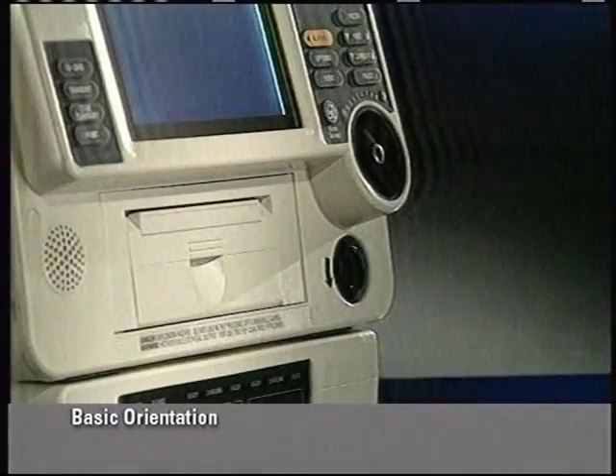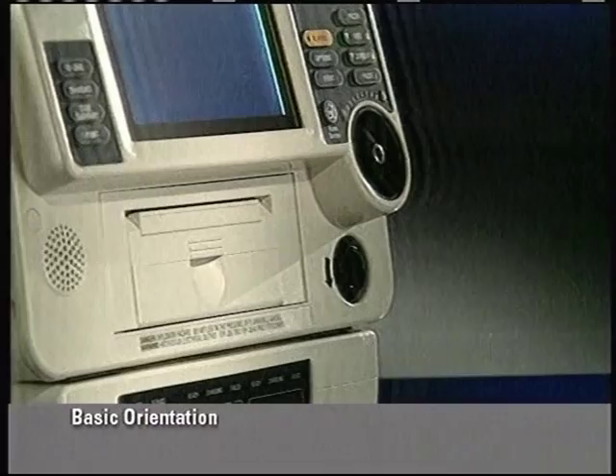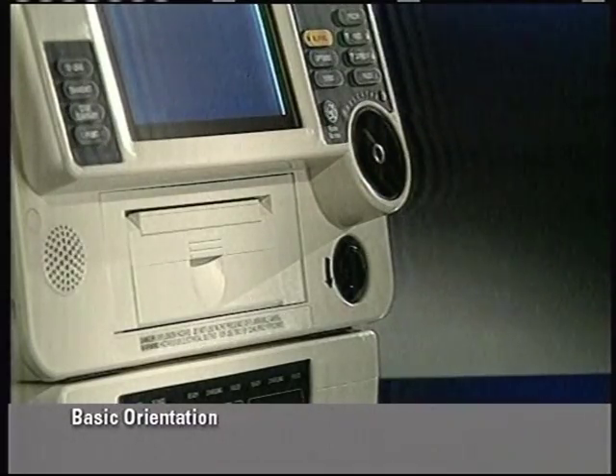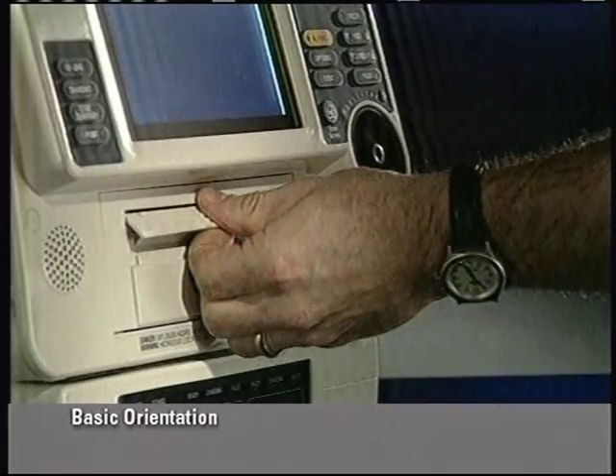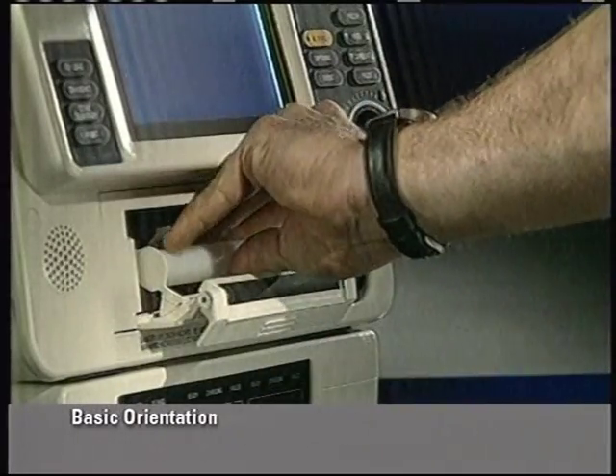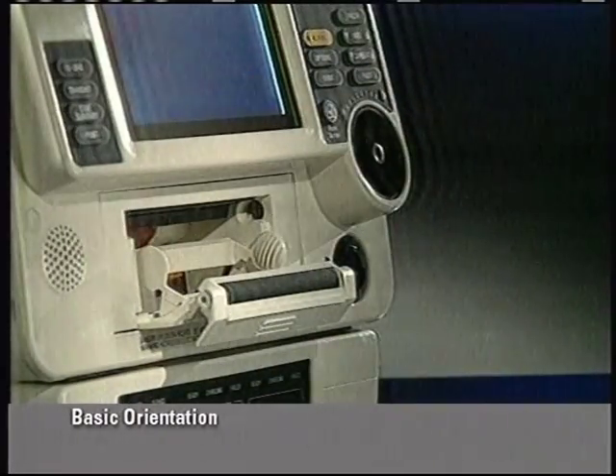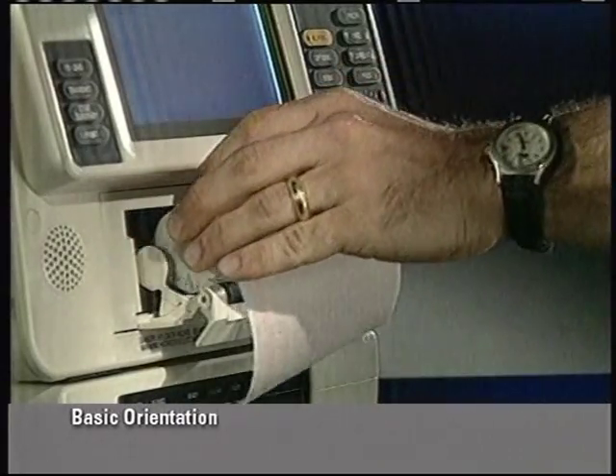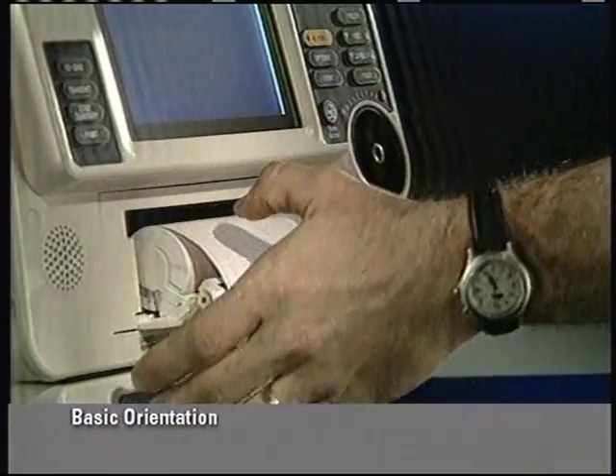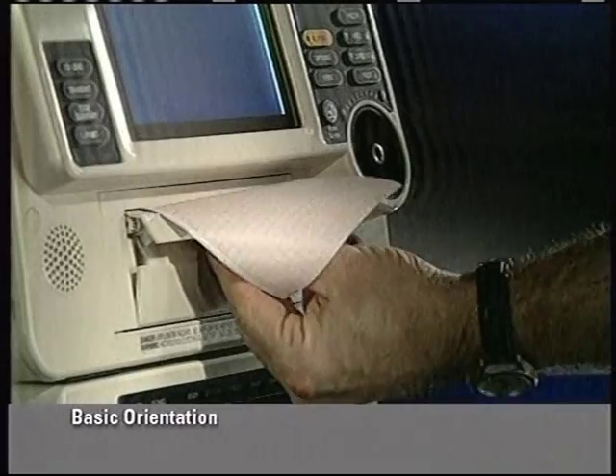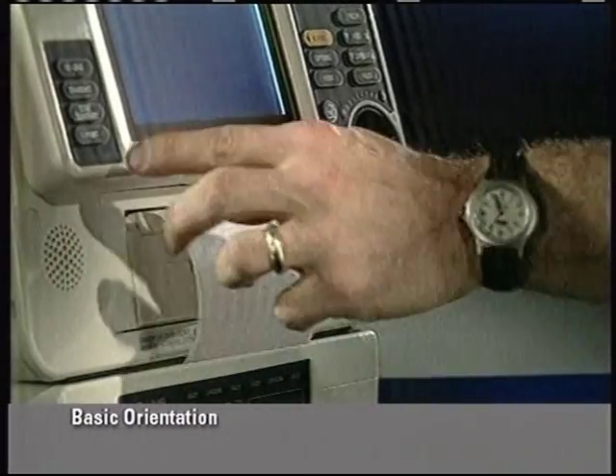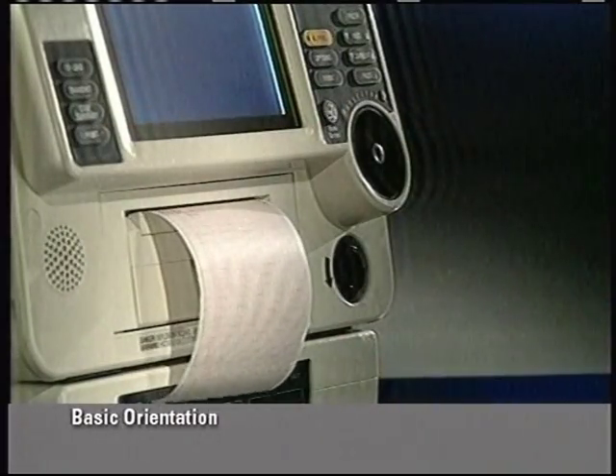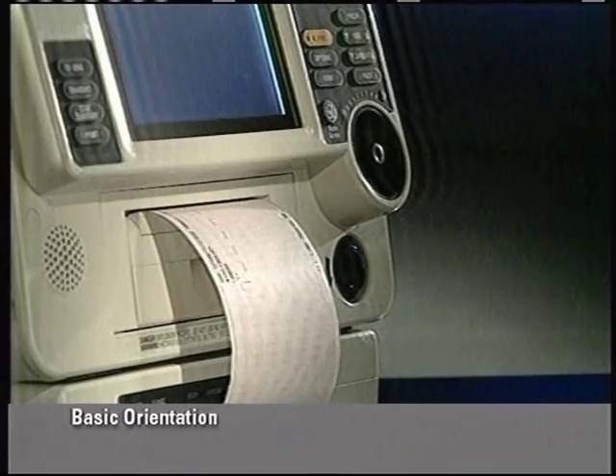The LifePak 12 defibrillator monitor may be configured with either a 50mm or 100mm printer. The 100mm printer is shown here. To change the paper, lift the printer door latch and pull out the door. Remove the empty paper spool. Insert the new paper roll with the graph side facing up and paper extending out of the printer. Close the printer door and push down on the latch until the door clicks shut. Press Print to check that the paper advances.